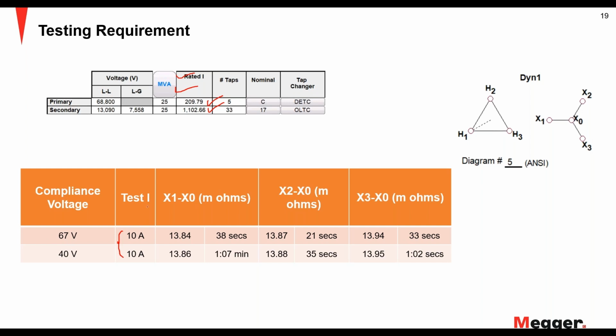What is the typical requirement, or what is the recommended current and voltage? I'll go through that in the next slide, but this is just showing you what compliance voltage does, how much faster the reading is. So for 67 volts, X1 XO, you get a stable reading in 38 seconds, and at 40 volts, you get the same reading at around 1 minute and 7 seconds. So you see the time difference there because of higher voltage.